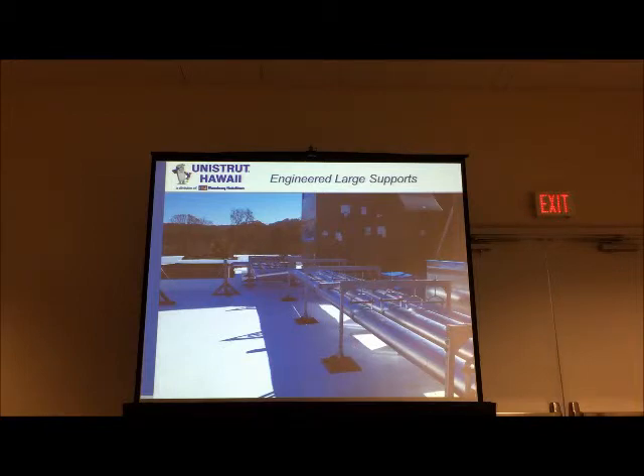This is being supported by clevis hangers. You've got 4 pipes, so your support is fabricated and spaced. You can see that if we were hanging this pipe inside a building, the spacing would be a lot farther than it is here on this roof. But because of the weight and the fact that we're trying to maintain that 2 pounds per square inch loading, the spacing of the supports is a lot closer.